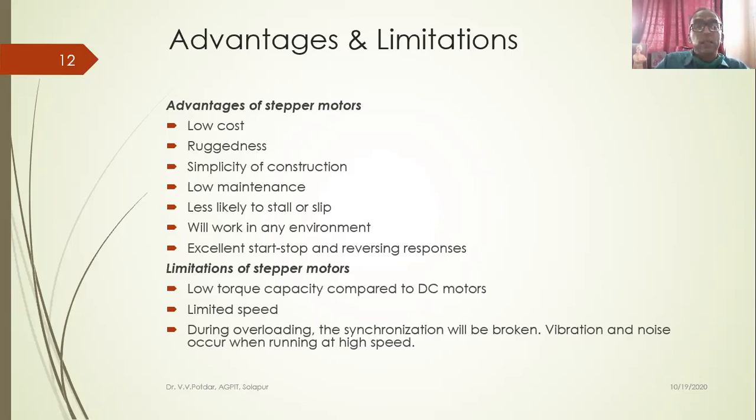Limitations: low torque capacity compared to a DC motor. This is a very big limitation. I can't move a much higher load by using stepper motors. Limited speed; during overloading the synchronization will be broken. So if there is more load torque on the stepper motor, it will no longer be synchronized. There might be some slip.